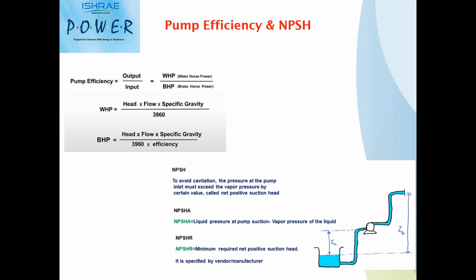If your NPSH levels are lower, in typical HVAC applications we face this problem whenever our cooling tower is on the terrace as well as the pumps are on the terrace. Our cooling tower is on the same level as where the cooling tower pump is installed. There we tend to face these problems because the required NPSH value at that particular point may be higher than available at the site. So it tends to suck the air from the atmosphere and cavitate at the pump. The pump will start vibrating, excessive vibration of the pump happens, and this will lead to lower flow rates and lower heads from the pump. So please ensure that your net positive suction head available at the site is always higher than the net positive suction head required by the pump.